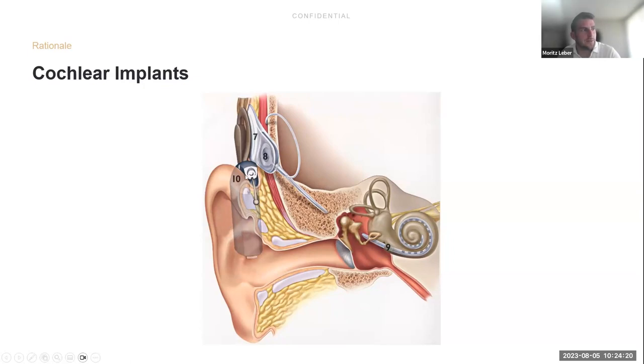by wearing a speech processor that is equipped with a microphone behind the ear that collects sound information, processes it, and transmits energy and information through a radio frequency, an RF coil, through the scalp to an implantable stimulator. You can see the receiving coil here as number 7. That then delivers or generates small currents or charge that are guided through a cable to an array of contacts, or an electrode array, that is implanted in the cochlea.